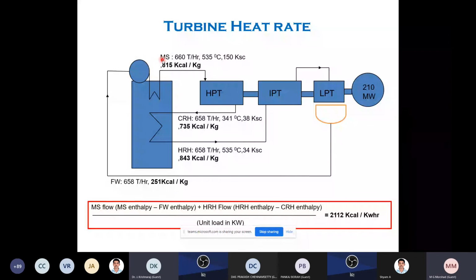First you have to note down the MS pressure, MS temperature, flow, and enthalpy. Main steam is 660 ton per hour, temperature 535 degrees centigrade, pressure 150 ksc. With temperature and pressure, you will automatically get the enthalpy. After that, cold reheat is coming. Same thing, for cold reheat you check the ton per hour, temperature, pressure, and enthalpy. Then after reheating in the boiler, it goes to the IP turbine. This is called the hot reheat. Then it goes to the LP turbine exhaust hood, then the condenser. And from the condenser, it comes to feed water and goes back.